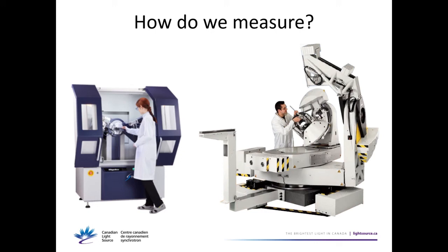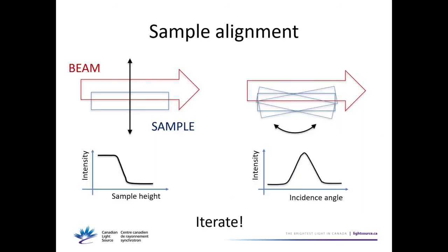To measure, you can use either a home diffractometer or a synchrotron. You put the sample in the center of the diffractometer — you want the sample in the center of the beam, not lower or higher, and parallel to the beam. To make sure the sample is in the center of the beam, you move it up and down and get a shadow intensity signal with a detector behind the sample. The shadow is when the sample is completely blocking the beam.